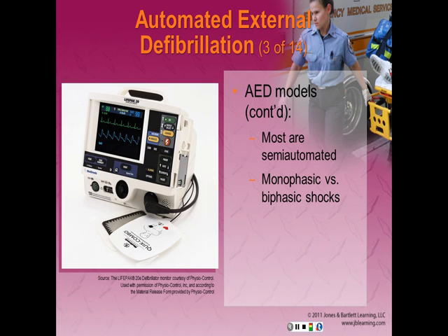The vast majority of AEDs are semi-automated. Shocks may be monophasic or biphasic. Biphasic shock produces more efficient defibrillation and may actually require a lower energy setting.